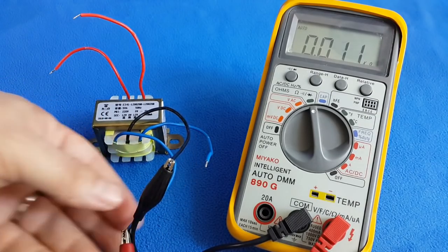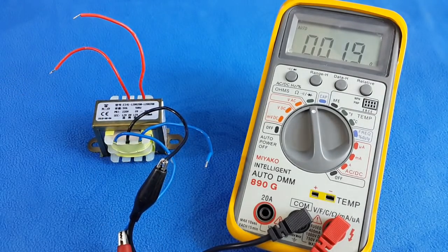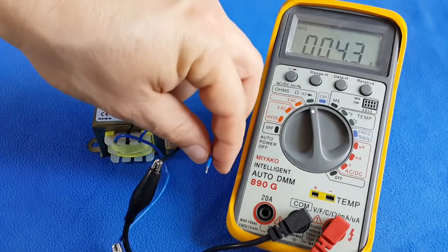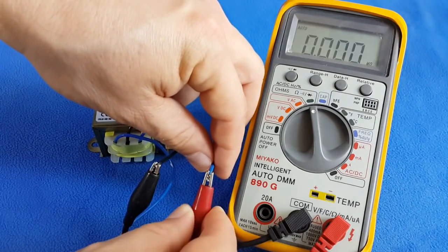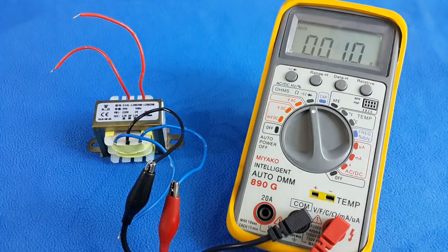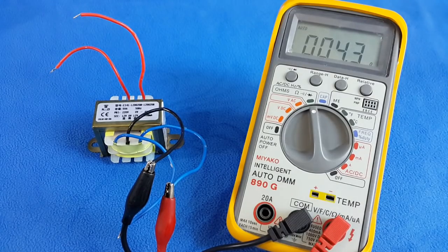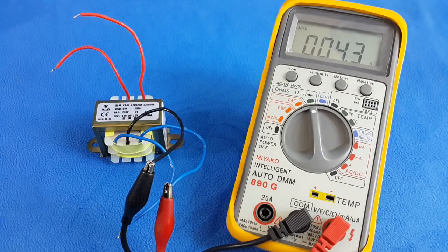It's a very low resistance, and this multimeter has high resistance on the cables, on the test leads. But I'm expecting something alike from the center tap to the other wire in the winding. This kind of test is just to find out which one is the primary and which one is the secondary line. This is not the official test to make a measurement in a transformer. This is other kind of test.